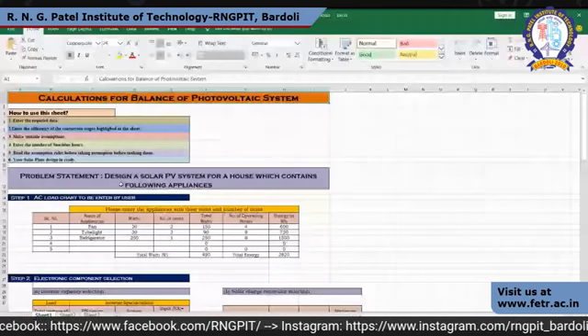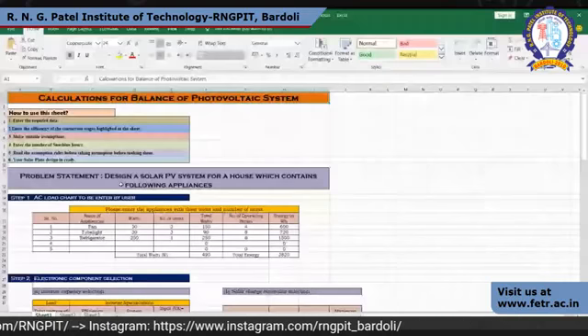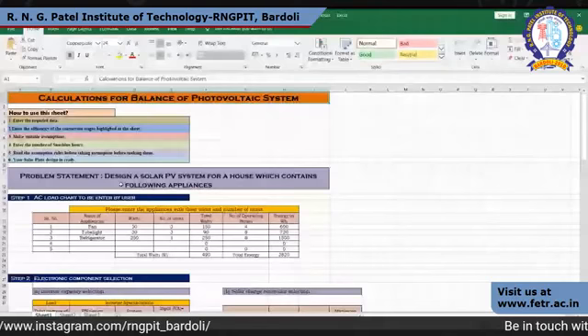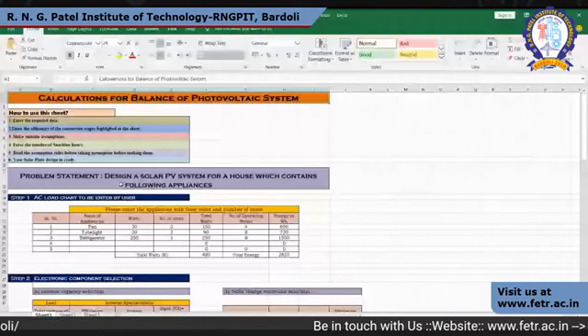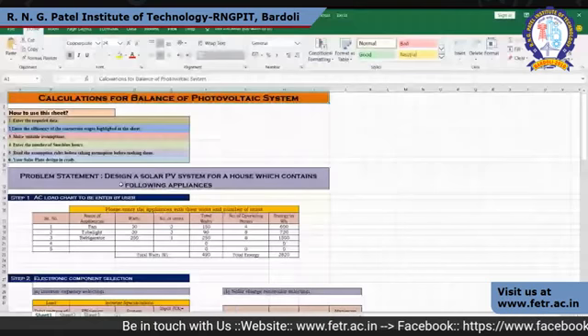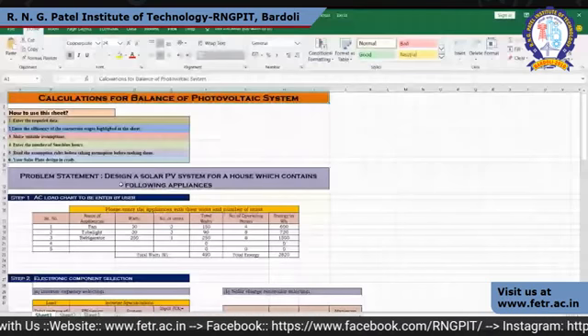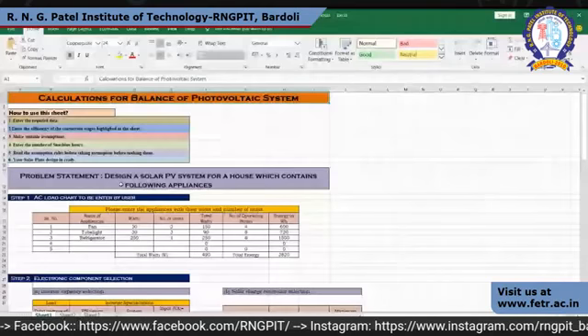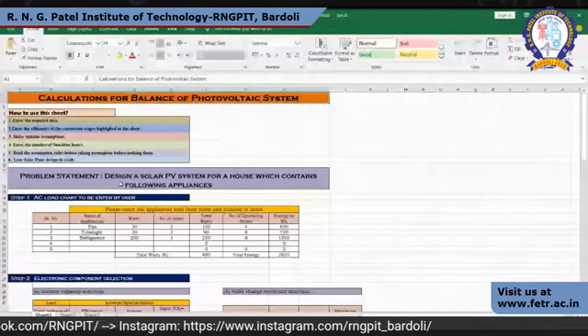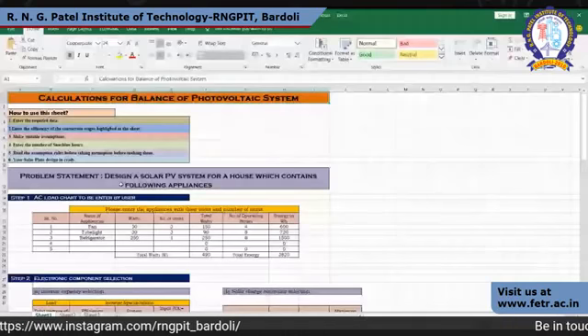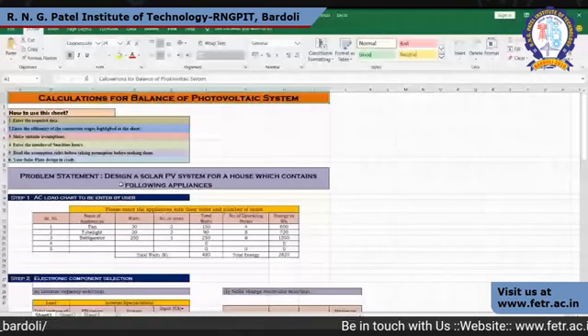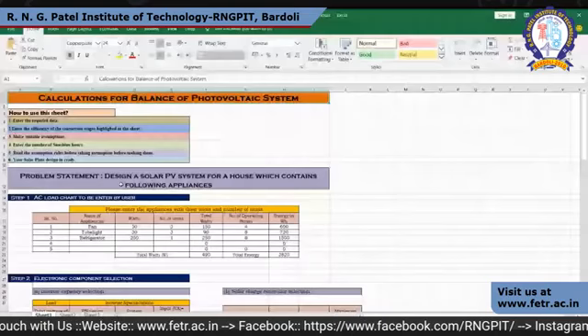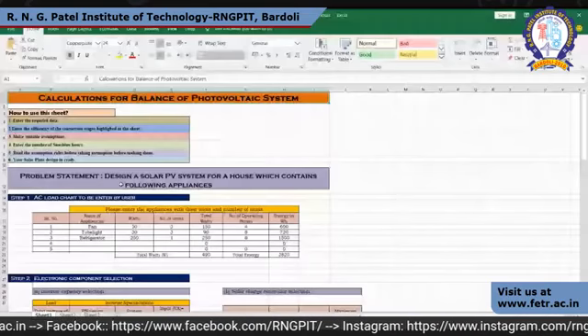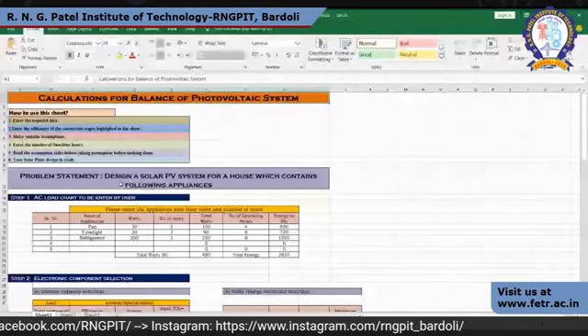Over here, assuming 70% depth of discharge means you can use only 70% of the stored energy. For example, if I have 100 chocolates, I can use only 70 chocolates, so 30 has escaped. So the first question is, why this much low DOD? We are assuming the worst data for the best design. Anyhow, you can assume 90 or 95 also. This could be assumed as 70 in this case, and accordingly your actual ampere hour will be there.